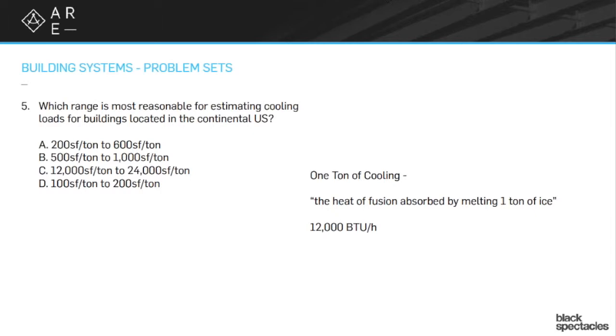If you haven't dealt with this kind of system, you probably haven't come across it before or thought about it this way. This is one of those numbers worth remembering. The number I always use is about 300 square feet per ton of cooling. So the range A is the right answer — 200 to 600.